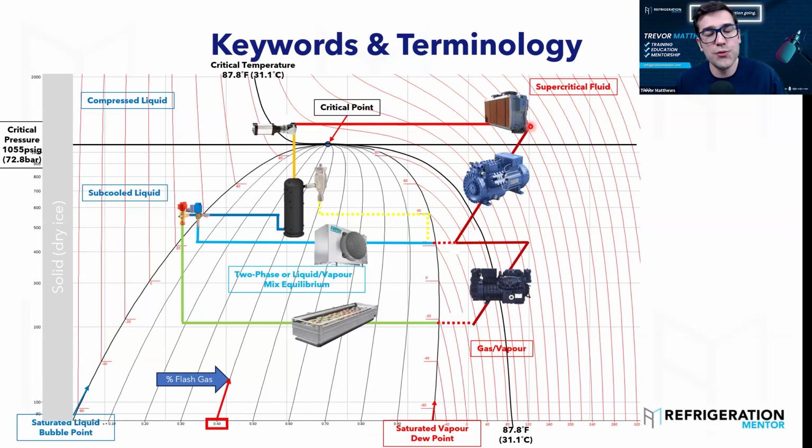So when that fluid hits that high pressure valve, we want as much liquid in that vapor as possible, or the least amount of flash gas as possible coming through that valve, which is so, so important. Because the less flash gas we have coming in through this high pressure valve means the less flash gas, in this example, going back through that transcritical compressor. And this here is key to understand.